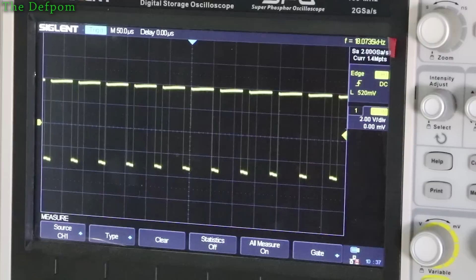I'll zoom into the scope so you can see a bit better. You can see some jitter there already, and as I turn the controls, it gets very jittery. Even though, you can see, my trigger point is certainly well within range. The trigger point is a little arrow on the side there, a triangle. So it gets very jittery. If I turn this control down, turn this control down, you can see those extra pulses in the middle there. You see them? So you've got the big pulses, then you've got little spikes in between. There are like 4 of them in that one.